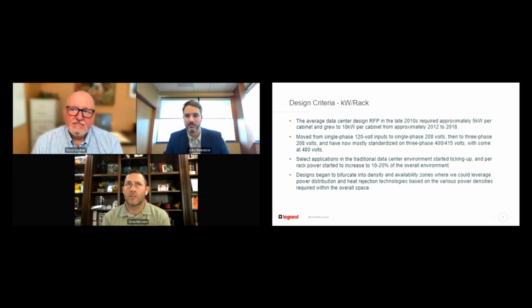And we were starting to see sort of availability zones emerge in data centers, where we would say, well, we have 100 cabinets, and 5 years ago, 100 of them were 5 kW. Well, now 20 of them are something different, and they're spread out. Or, one row is this, and then 2 cabinets in every other row are that other thing. And we were spreading load out for heat density because we wanted to sort of absorb that heat rejection into the ballroom of the room.